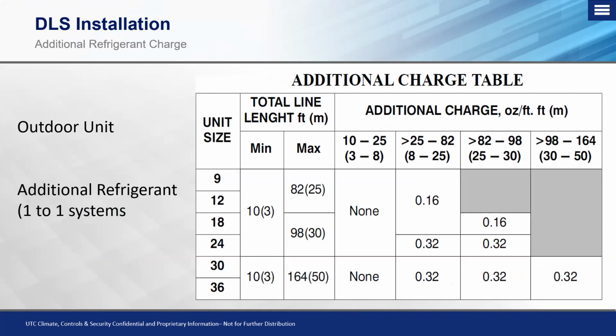So once we've pressure tested and we've evacuated, now we need to look at the system and say, hey, do we require any additional refrigerant charge? So with ductless systems, all of our line sets are based off of 25 feet for the charge that comes in the outdoor unit. Anything over 25 feet is going to facilitate some form of additional charge in ounces per foot. So in this case, if we look at a 12,000 single zone outdoor unit, our minimum line set length on a ductless system is 10 feet at minimum.